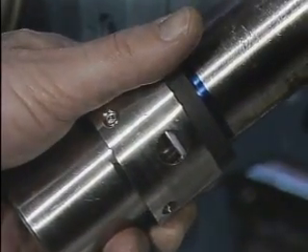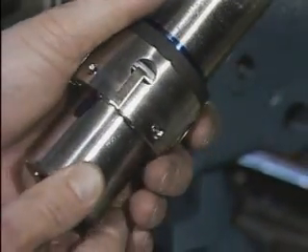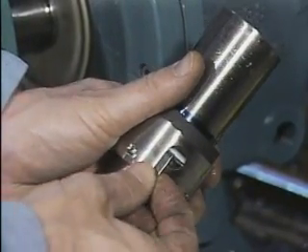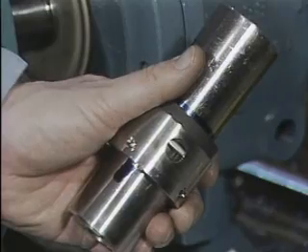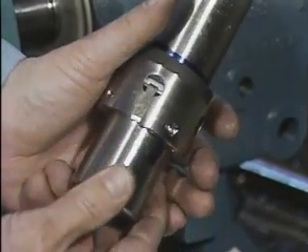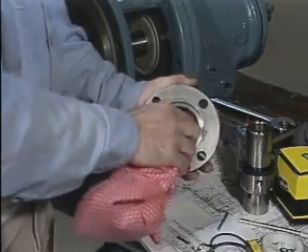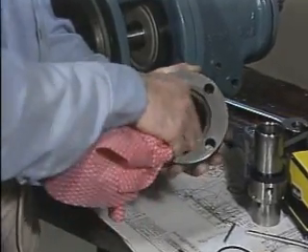Many seal manufacturers use retaining clips like the one seen here to compress the springs and hold the parts of the rotating element together before it's installed. These clips can be removed after the rotating element has been secured to the sleeve. The next step is to prepare the mating ring for assembly into the gland plate.